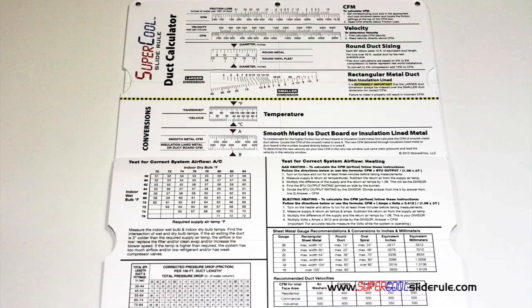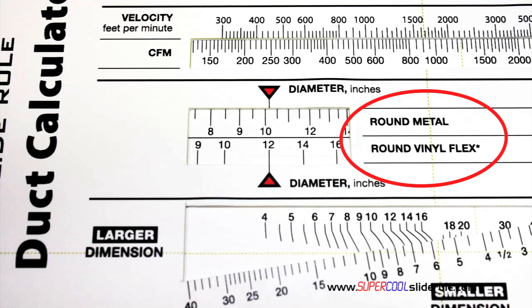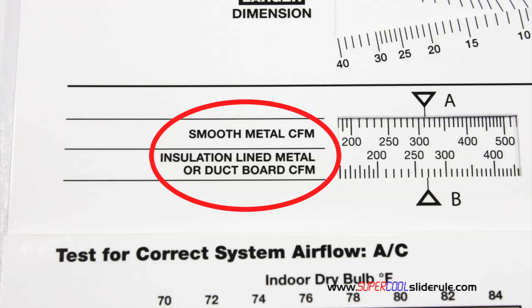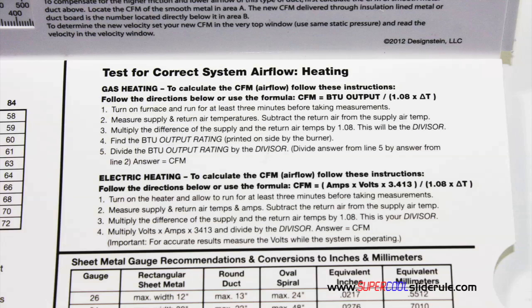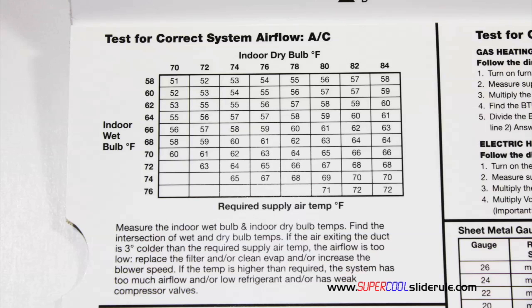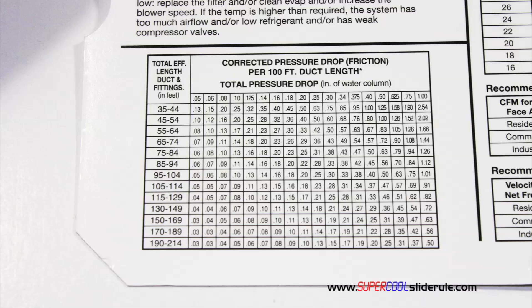Inside is packed with even more information. It performs sizing of both metal and flexible duct. It has the only direct reading conversion from smooth metal to insulation-lined metal we've ever seen. Most technicians have never been taught that if insulation is on the inside of the ductwork, you cannot size it with a regular duct calculator. It has step-by-step directions for determining airflow through a gas furnace, electric furnace, or an air conditioning unit, plus pressure drop multipliers for ductwork and recommended velocities.